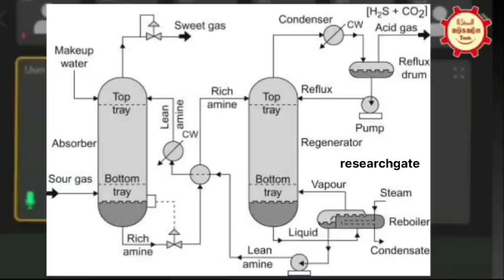We have an amine absorber where the bottom section is cladded and the upper section is carbon steel. So in that case, we have to do PWHT. But when it is cladded, I think we need to be careful. In the absorber, all the H2S and CO2 are absorbed by the amine and it comes to the bottom of the absorber. That region is clad for corrosion purposes, and once you are cladding it, it's a barrier. But PWHT is required because of amine service. So the upper part, which is unclad carbon steel, they are asking PWHT.